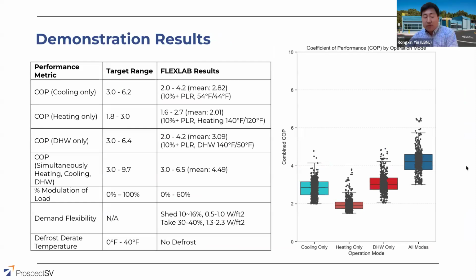All right. So I'm not going to cover the details of how we did our testing, but this is the overall demonstration project results from our phase one and phase two testing. And you can tell there are some constraints with our test bed for the heat pump testing, because the test bed is about 1,200 square feet, and during the testing period in the winter time, the max heating and cooling load is up to 3 to 5 tons, which is about 30 to 40% of the capacity of the unit. The unit we have is a 20-ton unit, and even though we disabled one of the compressors, it's still oversized for our test bed.